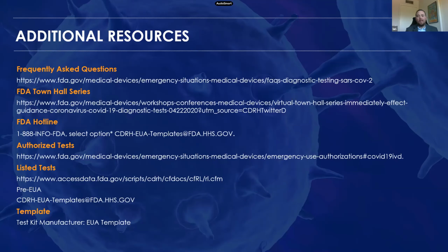That is updated continuously. And I would just say that if your test uses novel technology or a novel instrument or an extraction method that hasn't previously been reviewed by the agency, engage FDA in a pre-EUA dialogue. It's absolutely free. It's similar to the pre-submission, although they get back to you much more rapidly. And it's recommended if you have any questions before submitting your emergency use authorization request. Again, there's a test kit manufacturer EUA template provided by FDA that's specific to molecular tests right now. If you do email FDA, they'll give you some kind of unofficial guidance on the serological test information. And I am told that they are working on a serological test template that's specific to those types of tests. But right now, if you have all your validation data, engage them in dialogue, but they're recommending people use the molecular test template.